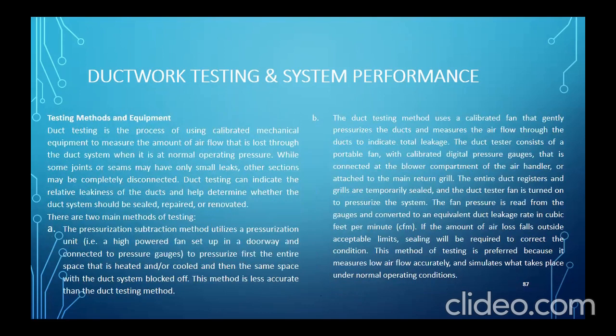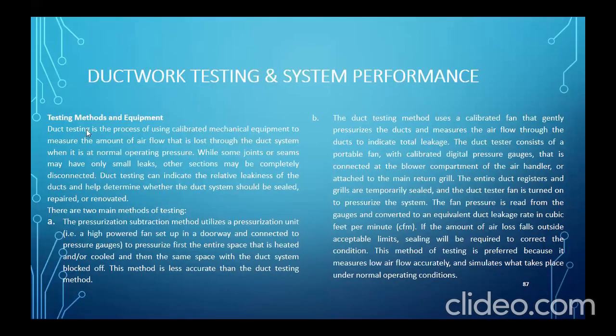So, testing methods and equipment. Ito. Duct testing. Duct testing is the process of using calibrated mechanical equipment to measure the amount of flow that is lost through the duct system when it is at normal operating pressure. While some joints or seams may have only a small leak, other sections may be completely disconnected. Duct testing can indicate the relative leakiness of the ducts and help determine whether the duct system should be sealed, repaired, or renovated. There are two main methods of testing.